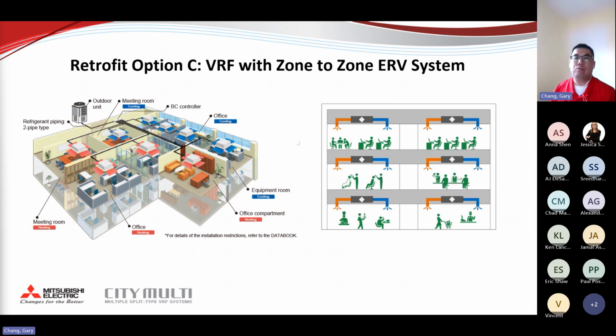So basically you can see we have to retain the existing ductwork and VAV box, but we don't need to utilize it. We can perhaps cap it, just not utilize it, because we have refrigerant piping from the condenser all the way to different fan coil units that you can see over here. Excuse me. Yeah, from the condenser to the different fan coil units with smaller refrigerant piping. So refrigerant pipe, compared to ductwork on the air side, can be smaller. And on top of that, we are also utilizing zone-to-zone ERV because people are in and out of the office a lot. So if nobody's there, just turn off the ERV or turn the ERV to low speed, instead of providing full building ventilation.